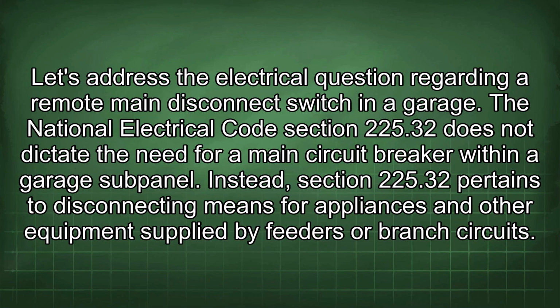Let's address the electrical question regarding a remote main disconnect switch in a garage. The National Electrical Code Section 225.32 does not dictate the need for a main circuit breaker within a garage subpanel. Instead, Section 225.32 pertains to disconnecting means for appliances and other equipment supplied by feeders or branch circuits.